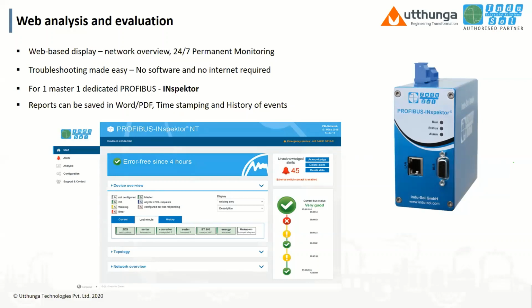When we open the inspector, this is the browser homepage. The homepage provides a complete overview of your network. You can see how many masters and how many slaves are in the network, and what the address of each slave is. There is no requirement for software, and also no requirement for internet. It is an IP-based system. You just need to take the IP and connect it to your system, and you will get the complete overview of the network. Moreover, you can print the reports in Word or PDF format. And the key point of the inspector is timestamping. What is timestamping? For instance, if any plant is running for 24 hours, most of the plants will be running for 24 hours, right?